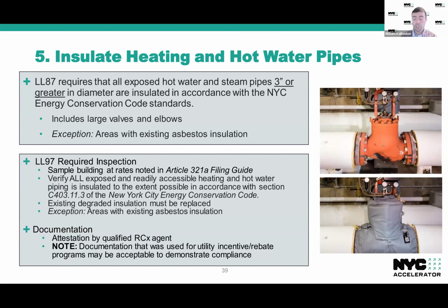In terms of the inspection requirement, the Local Law 97 RCX agent needs to sample all the piping throughout the building according to rates published in the filing guide, and verify that all accessible heating and hot water pipe is insulated in accordance with the Energy Conservation Code. That also includes that if there is existing insulation that is degraded or broken or just in bad shape, it needs to be replaced. Again, with the exception that if that existing insulation has asbestos, you don't need to touch it.